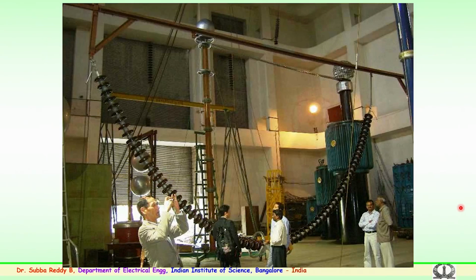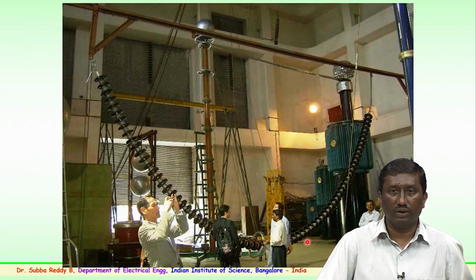So, this is one of the arrangements for a 765 or 800 kV transmission system in the laboratory. In a typical laboratory, the source is very important. The source should be able to deliver the required voltage. This is a 1 million volt, 50 kVA cascade transformer, where an insulator string in a V configuration is being erected. Tests like the voltage distribution across the insulators and the entire insulator string, the radio interference voltage and the corona are carried out before the insulator string is actually mounted in the field. Similar arrangements are normally used for various type tests or special tests in laboratories before the insulator string is energized in the field.